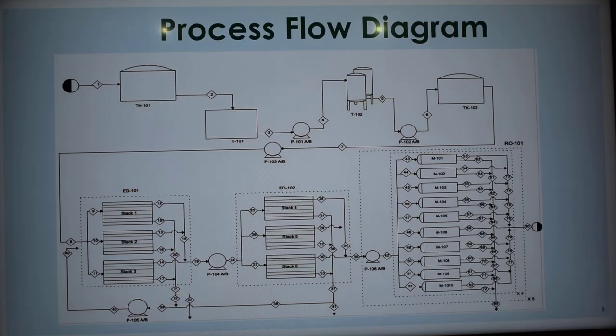But before allowing the water to this equipment, we need to do a pre-treatment. So we have sand filter and activated carbon filter. So the water flows to sand filter from a storage tank at 60 meter cube per hour. From there, the water flows to activated carbon filter. As these two processes are slow, the water flows and gets accumulated in the storage tank.